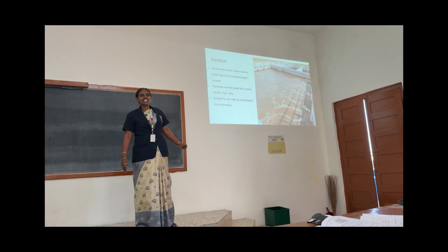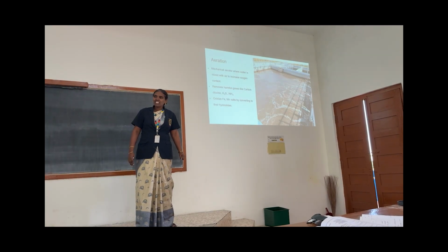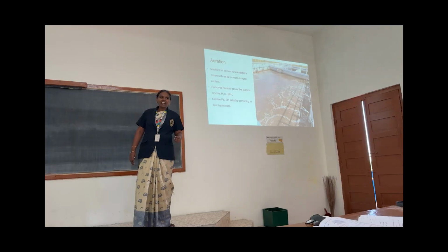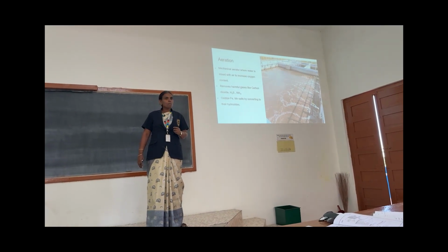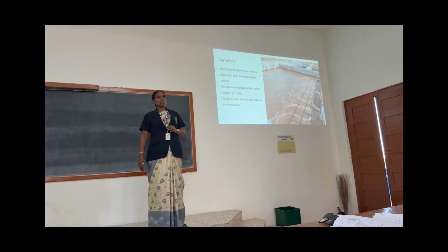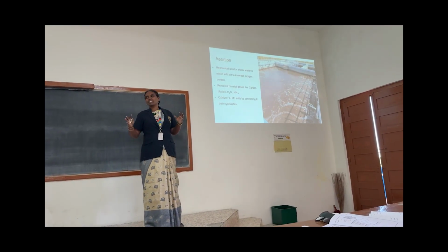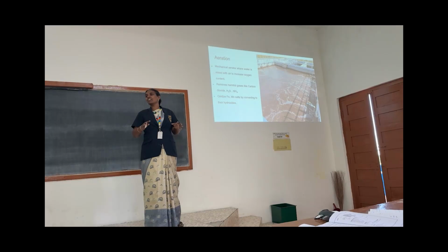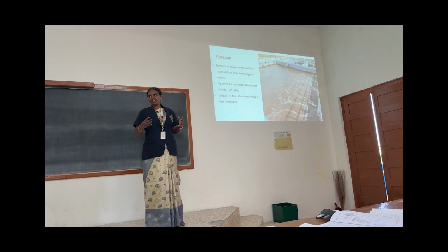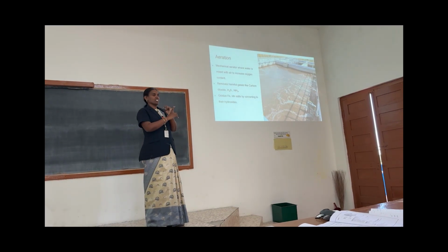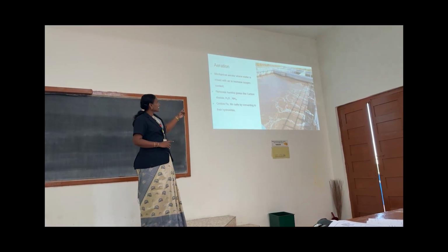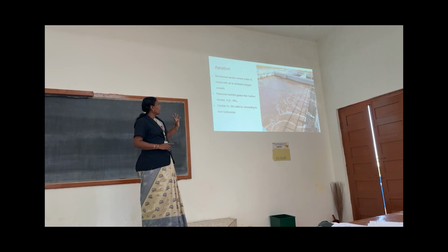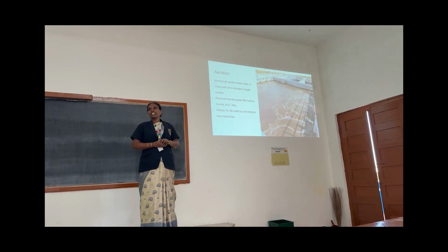What is H2S? Hydrogen sulfide. NH3 means ammonia. These harmful gases dissolved in water will come out if you are adding air. That is the first function. The second one: it oxidizes iron and manganese salts by converting them into their hydroxides.